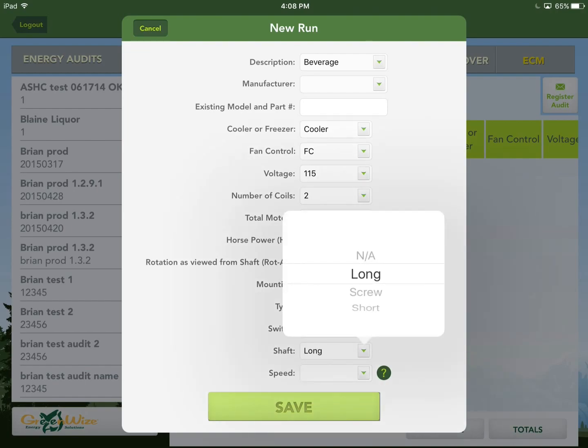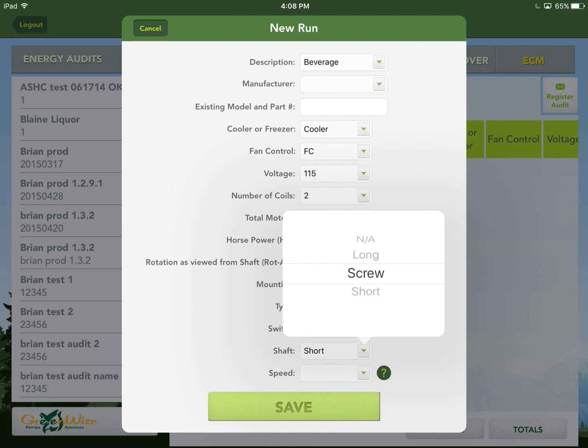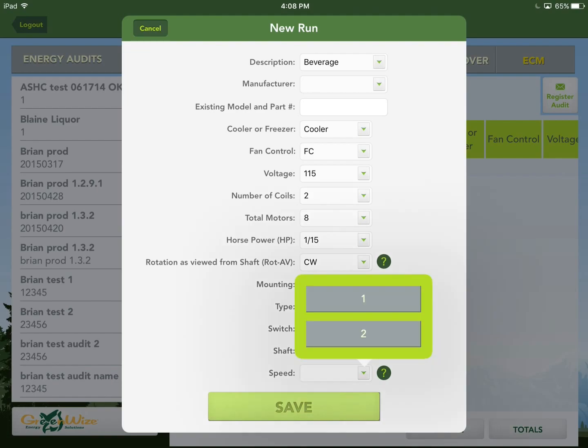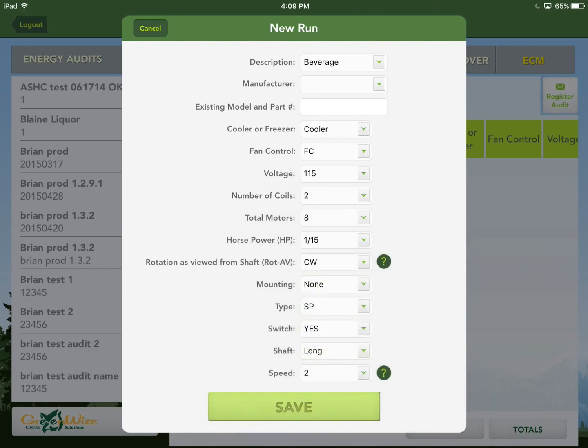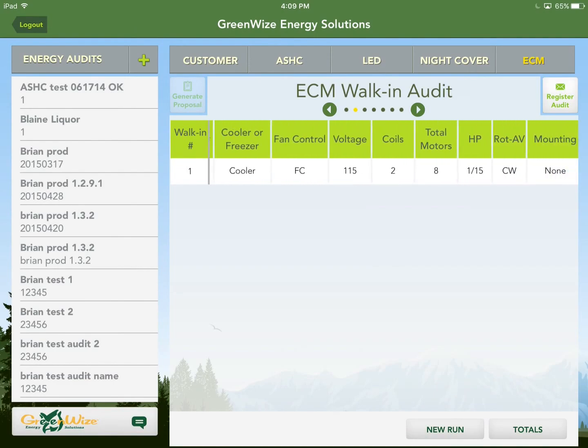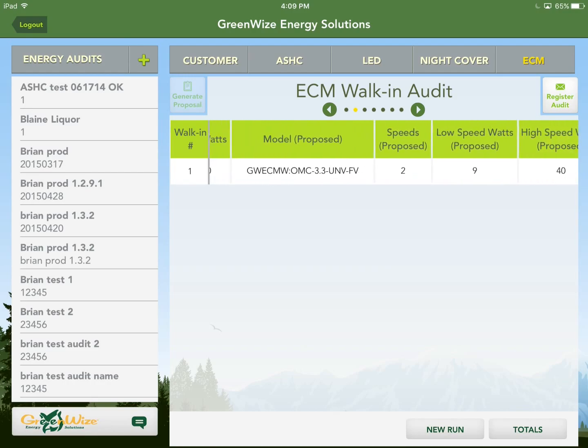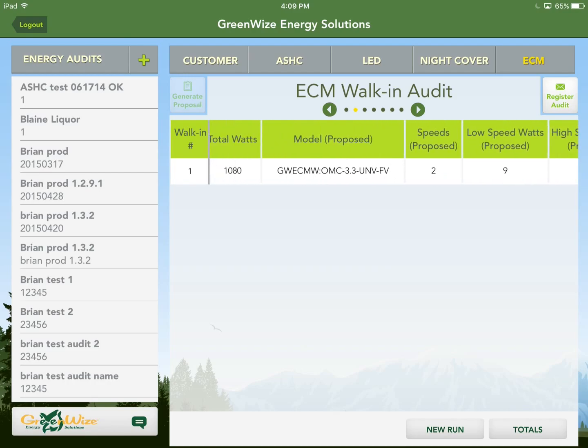For shaft type: long shaft is 2.6 inches, short shaft is about 1.75 inches. After some experience you'll easily tell the difference. The screw shaft has threads on it and uses a nut to secure the fan blade, whereas long and short shafts are solid. We'll choose long. Leave one-speed in case someone has old single-speed EC motor inventory, but 99% of the time you'll choose two-speed. Hit Save — it enters the information and auto-populates the correct motor model number for that application.